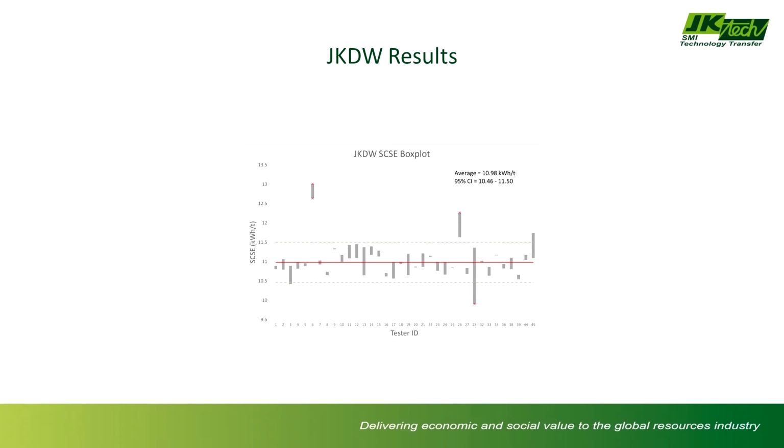Obviously, looking at this, you can just see by eye, something went wrong with those two testers. During our stat analysis, using the Grubbs test, we did classify those, or show that those are statistical outliers, and we removed them from the rest of the analysis. We also dug into those results and determined what the issues were. And to be honest, we lucked out with that lab. That lab shut down about a month after the comparative testing program. So it saved us a bit of work for patching it up.